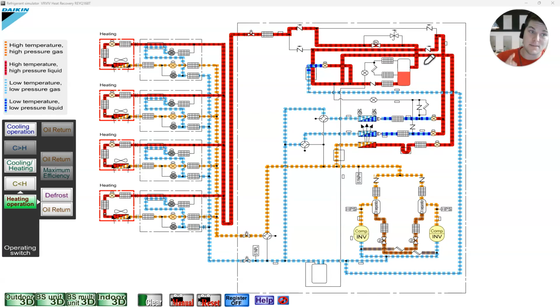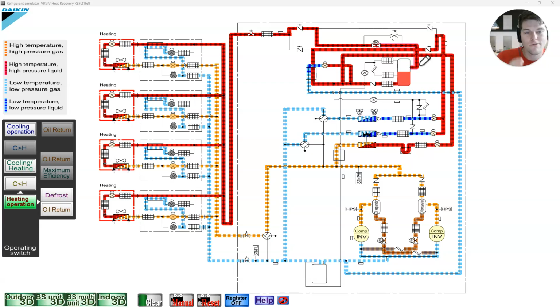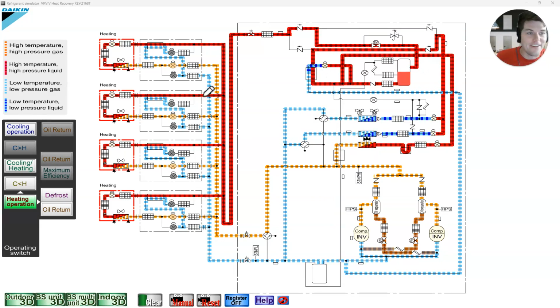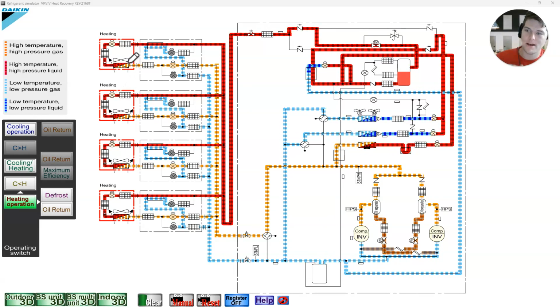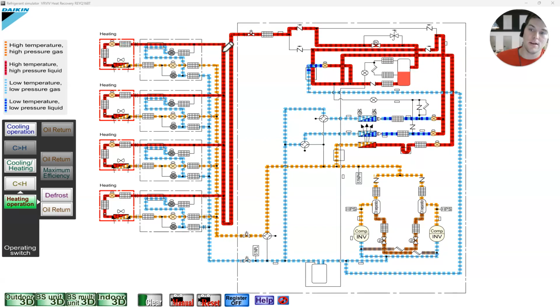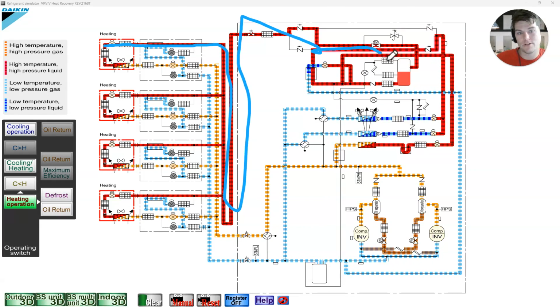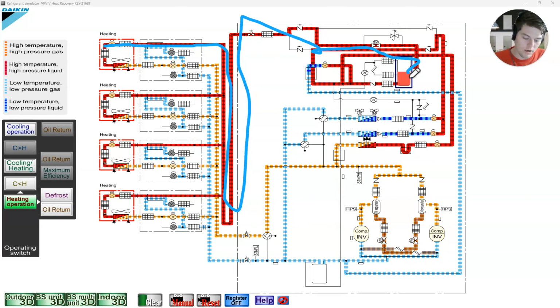That is an insane amount of subcooling. That's close to 90 degrees subcooling. How do I go from 20 to 90? Well, there's just a lot of liquid there, Roman. Duh, that's the answer. But is it though? Because let's talk about it. If I get liquid that comes from here and it goes all the way over here back to my liquid receiver, what do I know about subcooling and quality of subcooling?